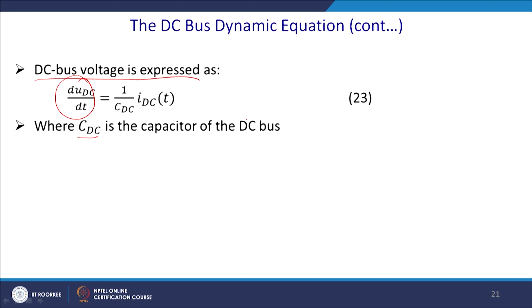In this hybrid generating system, 3 energy sources, PV panel, ESS and the electrical grid, are connected to the common DC bus via different power electronics converters. We have seen this in figure number 2, please recall that. According to the DC coupling, the capacitor current IDC is expressed as Im ESS plus Im PV minus Im inverter, where Im PV is the modulated current from the PV chopper, Im ESS is the modulated current from the energy storage chopper, and Im INV is the modulated current from the grid converter. Thus, we can express this DC bus current as IDC equal to C times dUDC/dt, where UDC is the capacitor voltage of the DC bus.